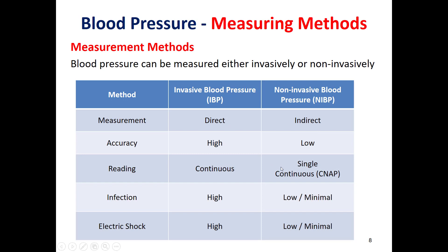Non-invasive blood pressure can be a single reading or a continuous reading. Single reading is typical in the oscillometric method, used in vital signs and patient monitors. Continuous reading is available in CNAP technology — the acronym for Continuous Non-invasive Arterial Pressure. However, invasive blood pressure has drawbacks including high infection risk and a high possibility of electrical shock, whereas non-invasive blood pressure is safer regarding both infection risk and electrical shock.